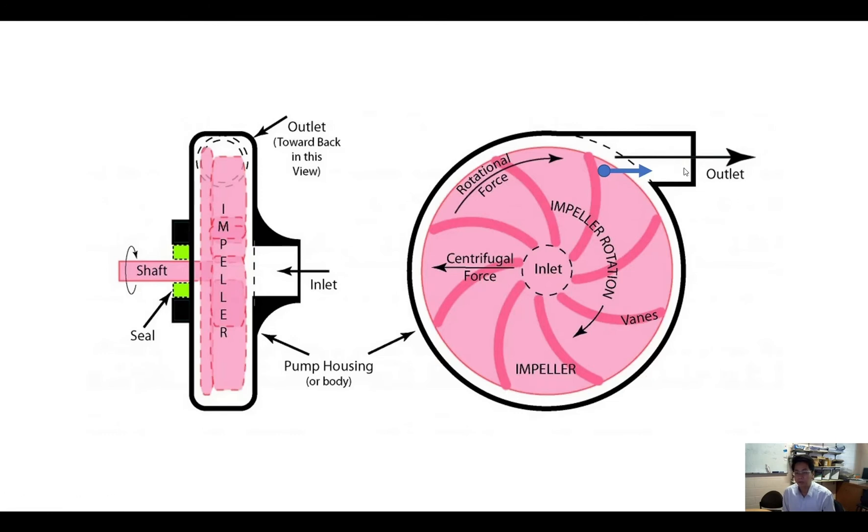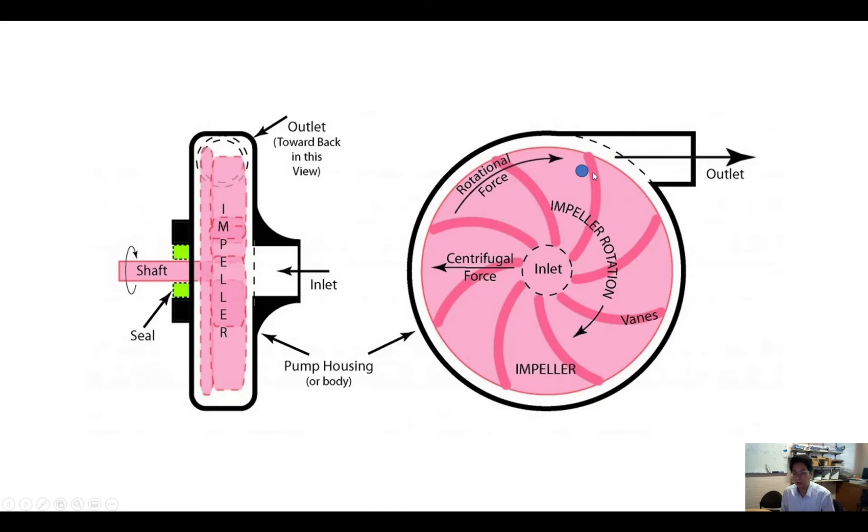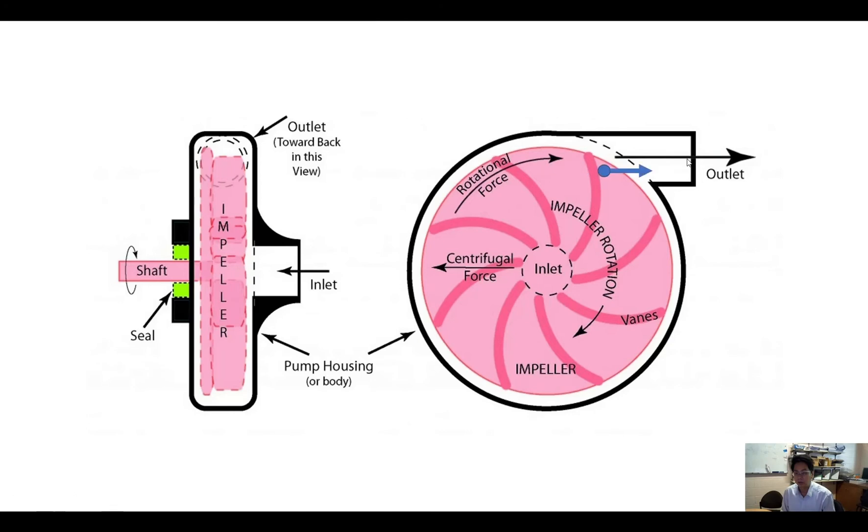However, when you reverse the rotation of the impeller and you have the water molecules on the other side, when the blades come and hit it, it will generate a force that hits the water molecules inside the pump and go to the center. So the outlet now becomes the inlet. So please ensure that you have the right rotation of your pump.